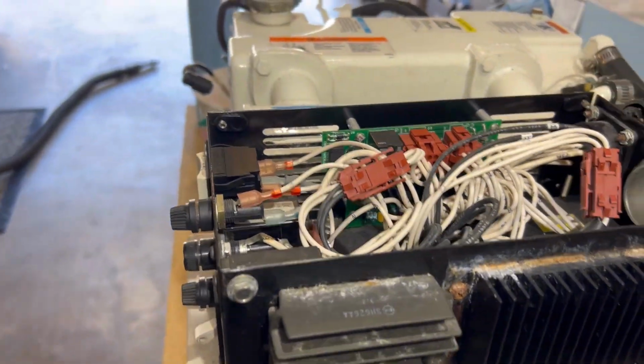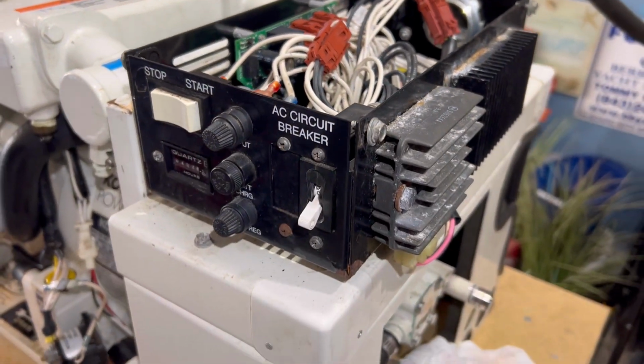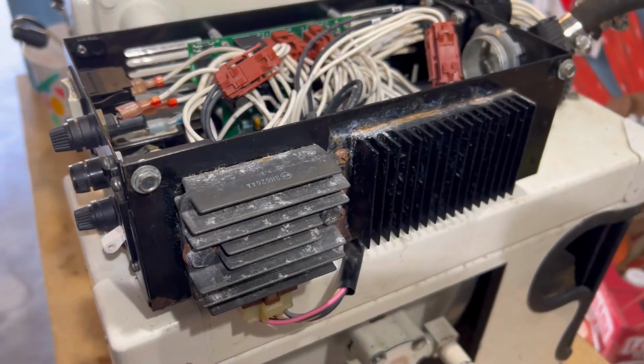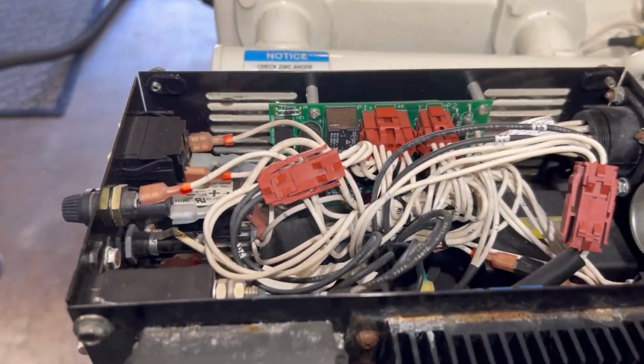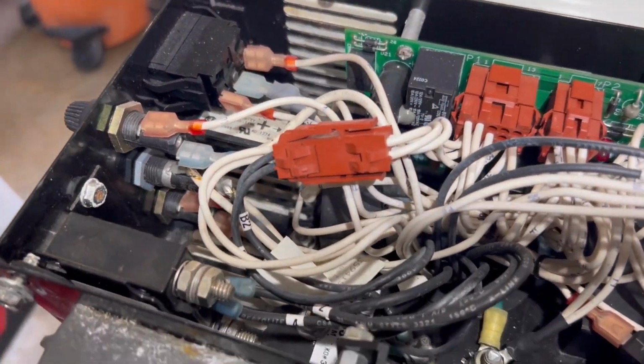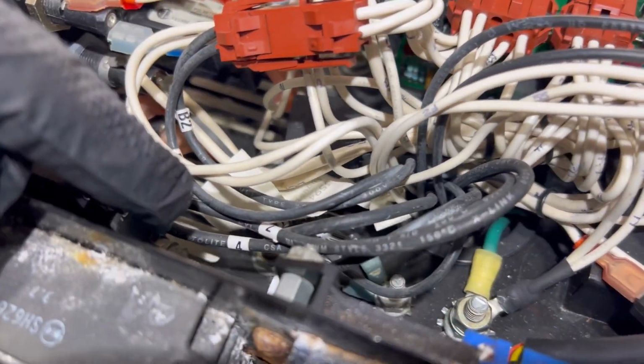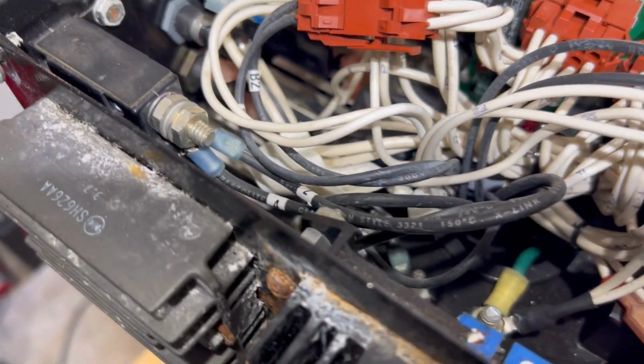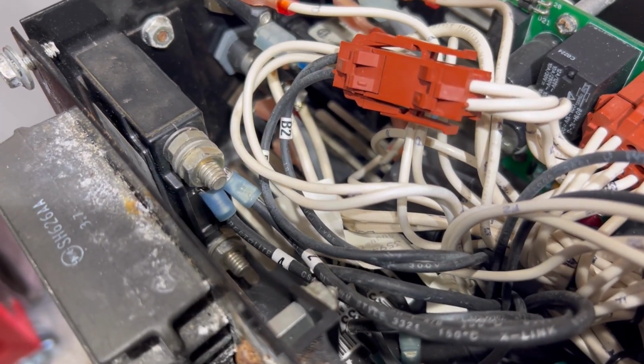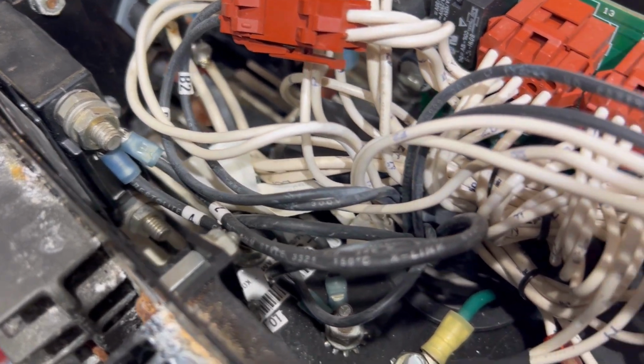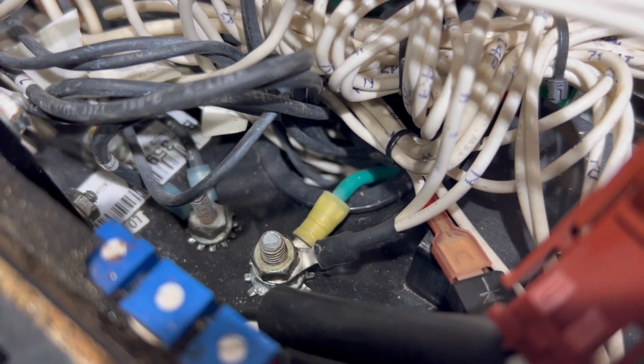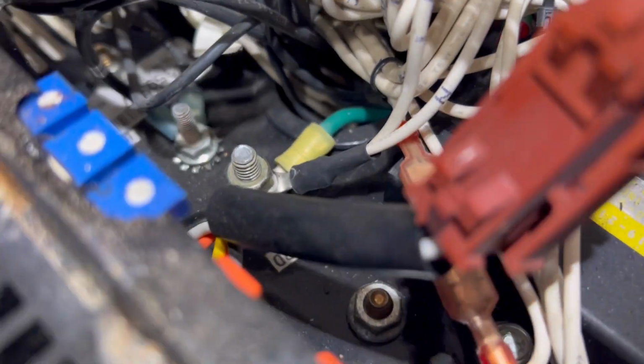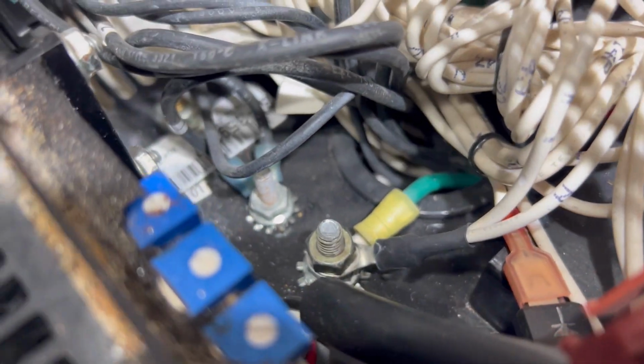On this particular configuration, we have a single circuit breaker for 120 volt, 60 hertz operation. So we have wires 2 and 4 going to the top of the circuit breaker, and then 1 and 3 are going to the L0 stud right there.